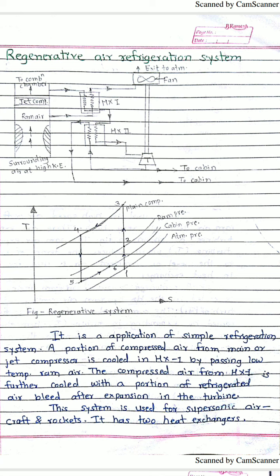One key difference: in the simple air refrigeration system there is only one compressor, one heat exchanger, and one turbine. In the bootstrap system we use two compressors, two heat exchangers, and one turbine. In this regenerative air refrigeration system we use one compressor, two heat exchangers, one turbine, and a circulation fan. As usual, the process begins with sucking in ambient air.